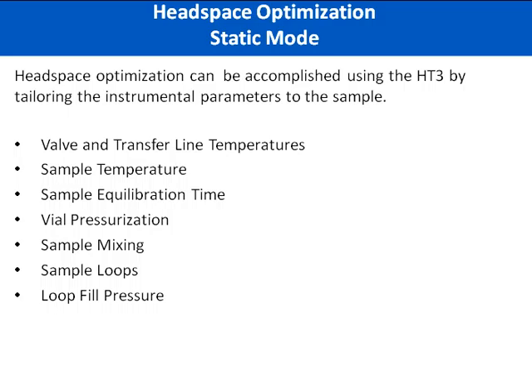The sample temperature plays an important role on any type of headspace analysis, as higher temperatures of the sample will shift the equilibrium to favor the headspace. This temperature is going to be limited by the boiling point of your sample solvent and the thermal stability of the sample components. The equilibration time is the time required to reach equilibrium, and it's dependent on your sample matrix, the analytes being determined, and the temperature.